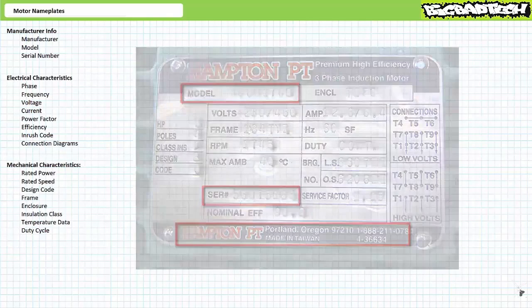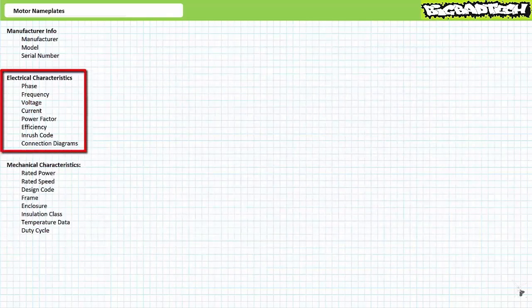530-75185. The next category on a motor nameplate pertains to the electrical aspects of the motor in question. The most important of these entries specify phase, frequency, voltage, current, power factor, efficiency, inrush code, and connection diagrams.